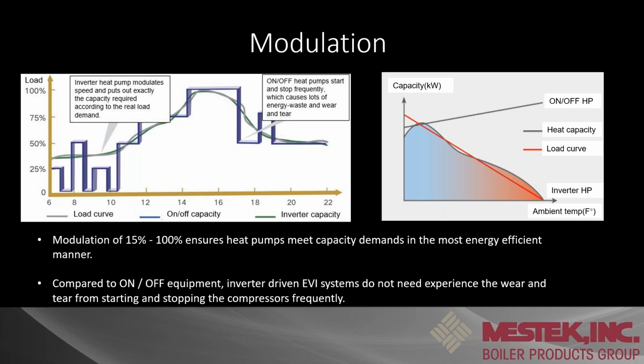So your purple line here is an on-off unit. As it hits temp, it shuts off, goes through its offset, then comes right back on and overshoots and does the same thing. With an inverter, just like a modulating boiler, we want to keep this thing running and maintain the temperature needed. So you're seeing a nice straight line instead of these ups and downs.